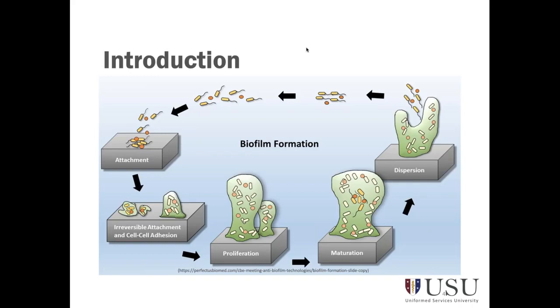You probably won't be surprised that when you get it out, it's not going to be anywhere near clean. So when the bioburden is left inside the instrument, essentially what you see right there on that graph, in that picture, is that those bacteria begin to replicate or multiply. As they multiply, they make this biofilm, and they do this to protect themselves, obviously, from the external environment. As they continue to build, eventually they burst, and they go to a different area of the instrument and start the cycle all over again. So this is why it's important that instruments are cleaned completely, because as you already know, if the instrument cannot be cleaned, it cannot be sterilized.